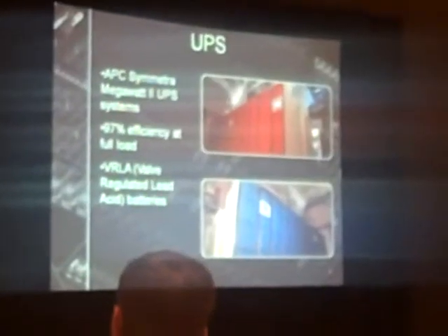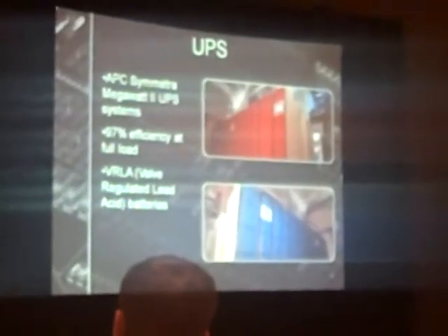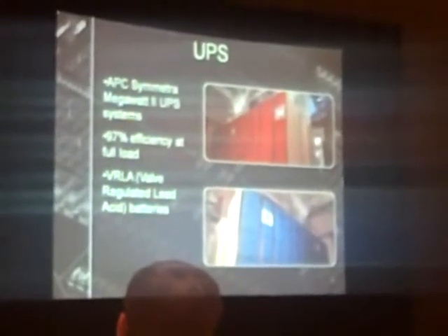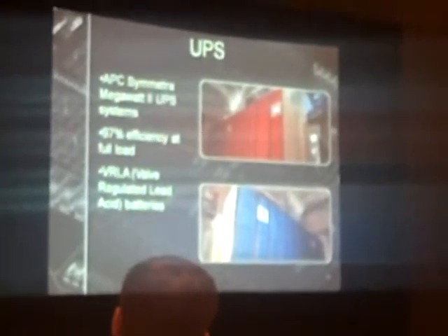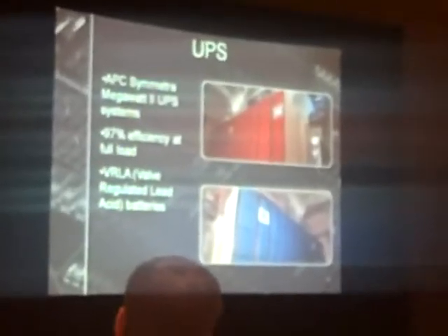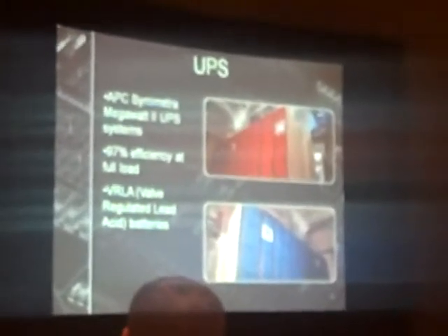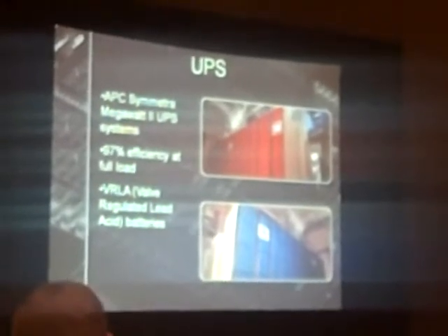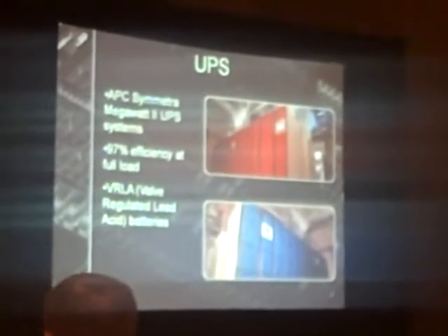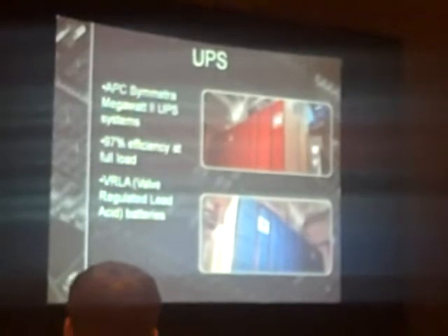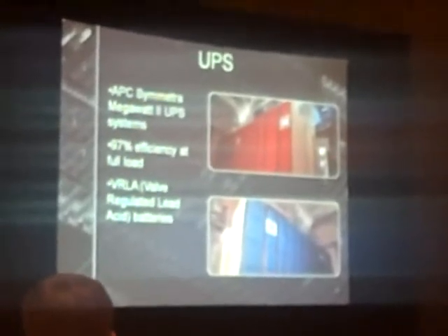UPS systems: we use APC Symmetra megawatt UPS systems. Each one has valve-regulated lead-acid batteries, each with a 5-year shelf life, but we replace them every 3 years just to be safe. We also monitor every single battery inside every single module for charge and ampacity. Just because a battery has a charge doesn't necessarily mean it has enough juice to run anything, so that's why we monitor for ampacity as well.